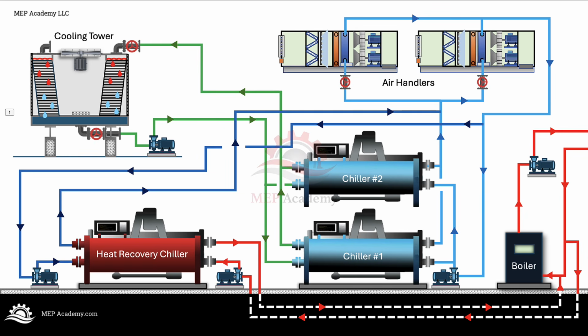The important point is that the controls must decide what the system is trying to accomplish. Is the heat recovery chiller running because the building needs chilled water? Is it running because the building needs hot water? Is it running because both loads are available? Is excess heat being rejected? Are the boilers enabled? Are the cooling towers enabled? These control decisions are what make the system work.